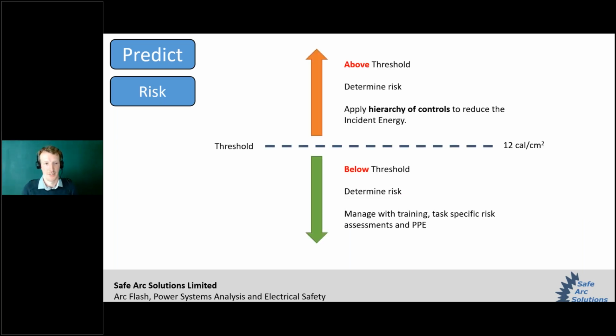One approach that a lot of our clients have found useful to simplify this a little bit is to use the concept of a threshold incident energy level. So for example, you could say 12 calories per centimeter squared is going to be our threshold value, and then anything above that you want to try and take measures to bring it below the threshold. Anything below the threshold can then be managed through mitigation measures around knowledge, training, competency, risk assessments, and the use of PPE, because you've got a generally lower incident energy at that point.